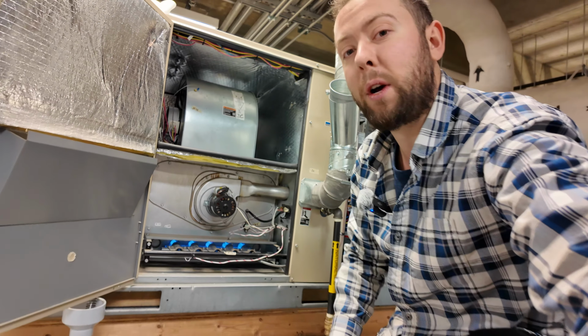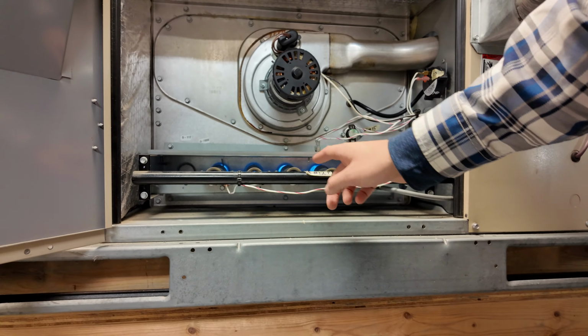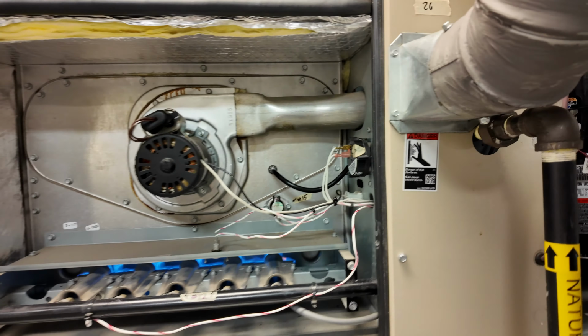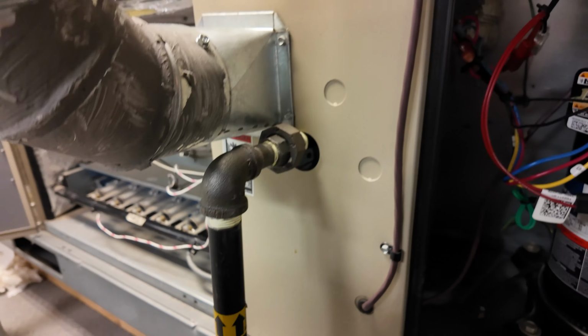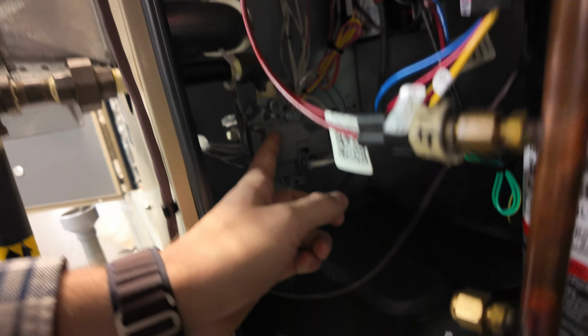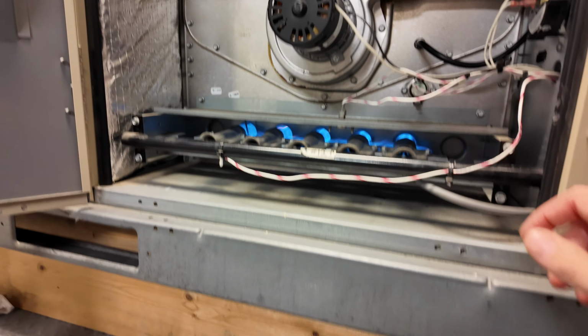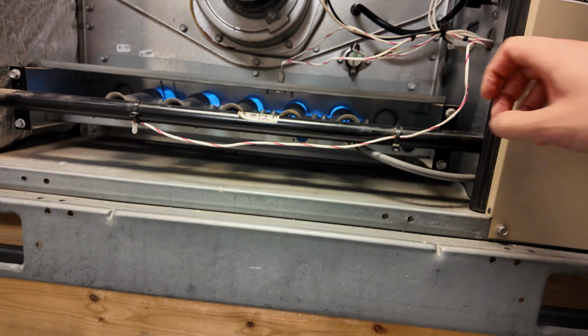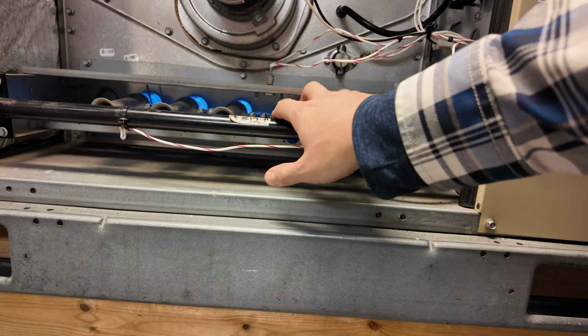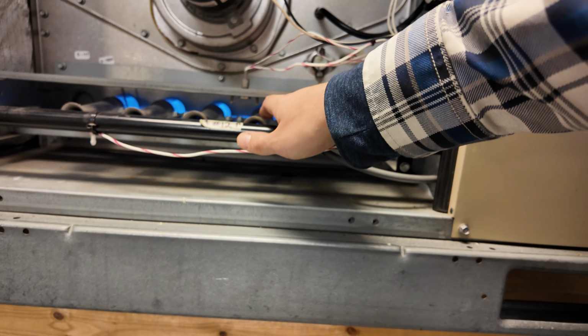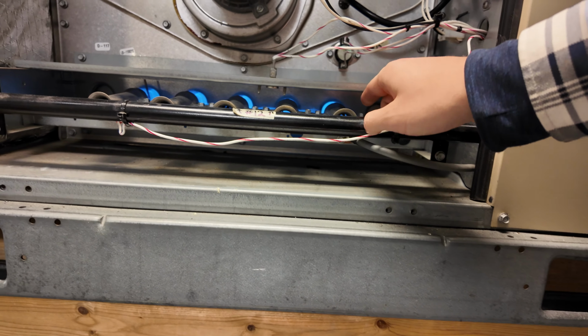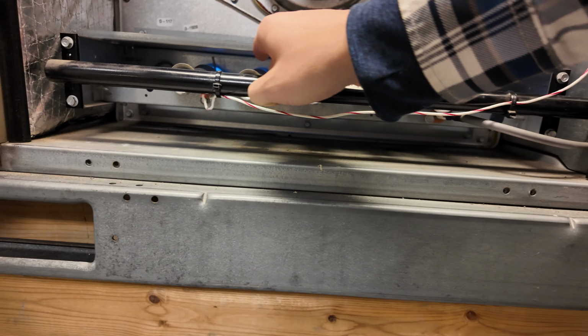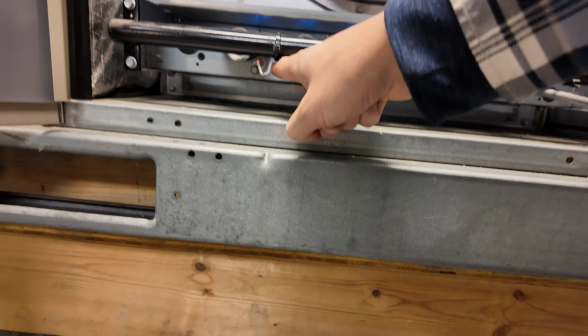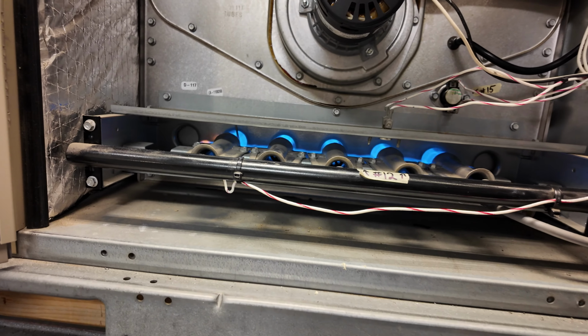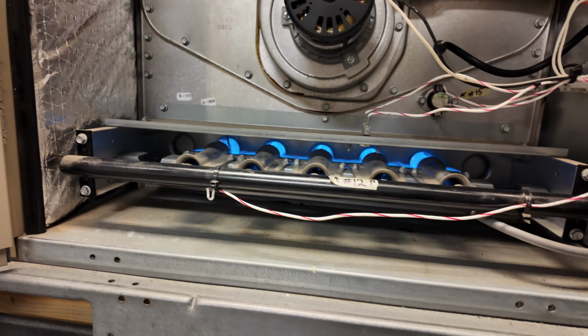And you just heard, once it says the safeties are good, right here is where the burners are. But over here, if you follow the gas line, comes around the corner here, and the gas valve is just right here. So the gas valve is going to open. Then we have an igniter cable here. It goes to the igniter. The gas will come down the manifold, go through the venturi tubes and mix with primary and secondary air, and then it will be lit by the igniter, and the burners will light across, and the last burner here is where the flame sensor is located, and then it will detect flame through flame rectification.